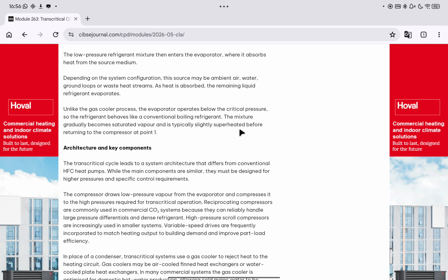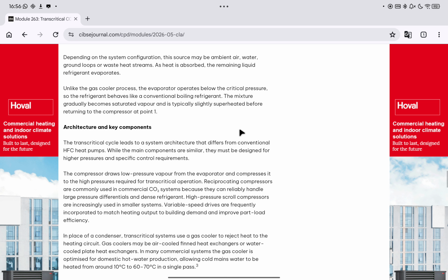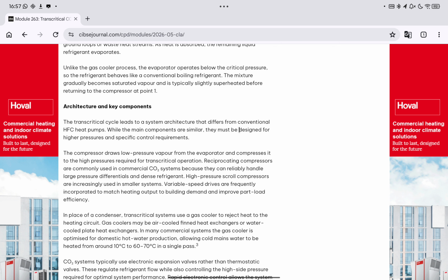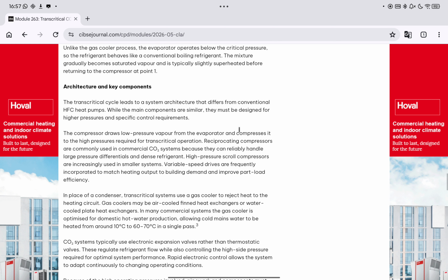Architecture and key components. The transcritical cycle leads to a system architecture that differs from conventional HFC heat pumps. While the main components are similar, they must be designed for higher pressures and specific control requirements. The compressor draws low-pressure vapor from the evaporator and compresses it to the high pressures required for transcritical operation. Reciprocating compressors are commonly used in commercial CO2 systems because they can reliably handle large pressure differentials and dense refrigerant. High-pressure scroll compressors are increasingly used in smaller systems. Variable speed drives are frequently incorporated to match heating output to building demand and improve part load efficiency.